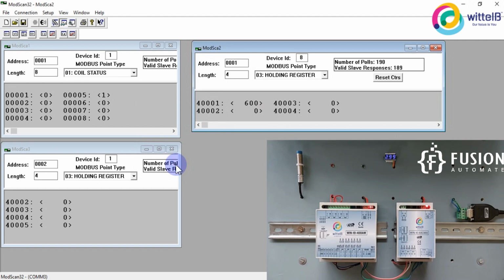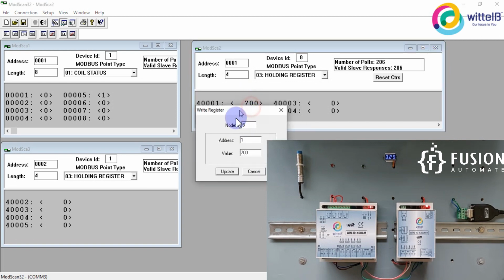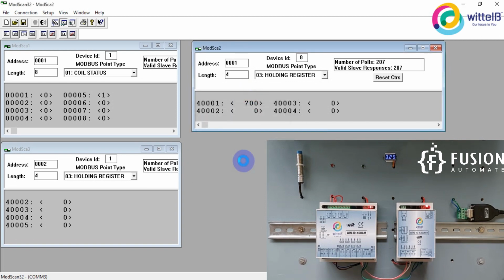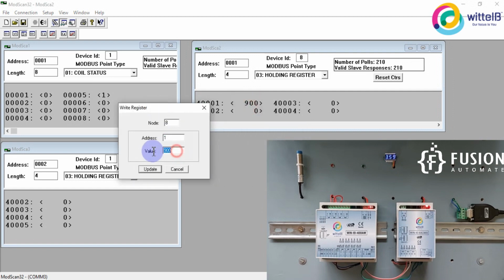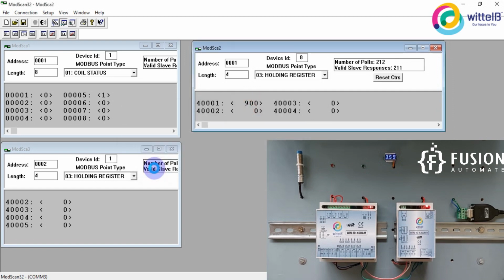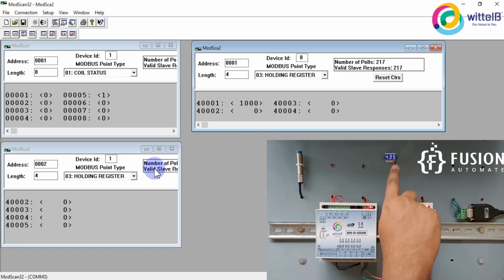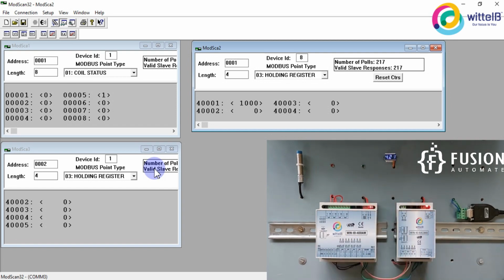then you will see the value change, like 3.22 is there. So if you increase the value up to 900, then you will see much more update on this DC voltmeter. 3.59. If I increase the value up to 1000, then you will see around 4 volts on the DC voltmeter. And so this analog output card is providing voltage to this DC voltmeter, and according to that voltage, the value of the DC voltmeter is varying.